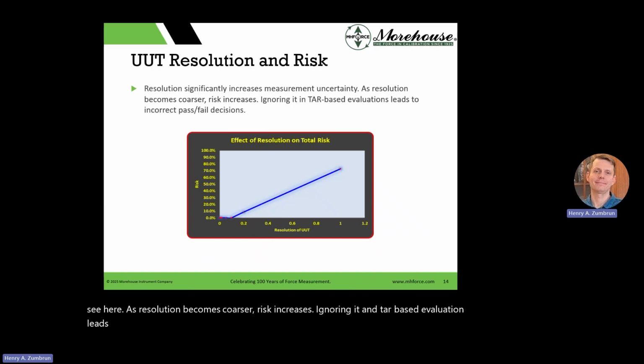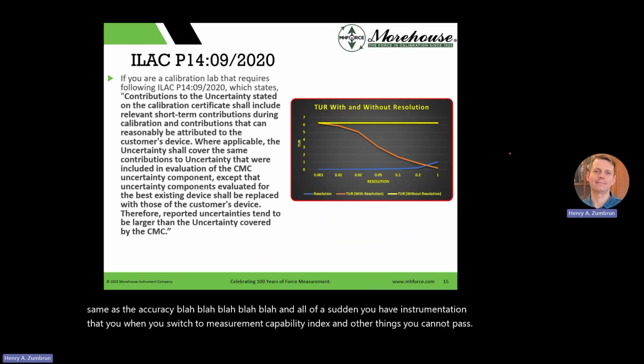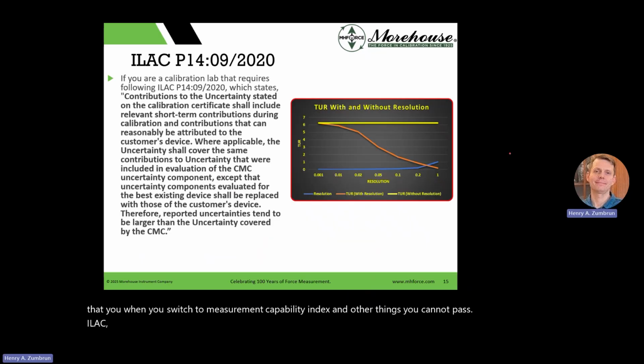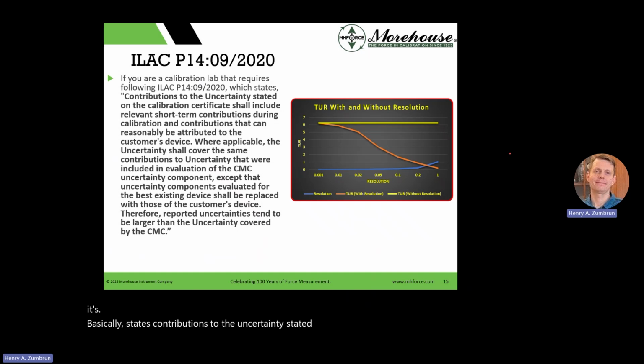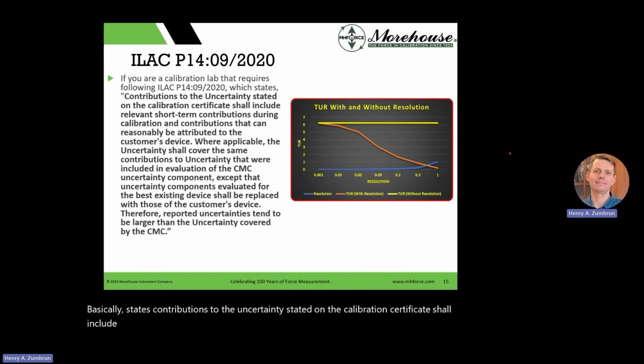So this is what happens. Manufacturers say, hey, the resolution is the same as the accuracy, and so on. And all of a sudden you have instrumentation that, when you switch to the measurement capability index and other things, you cannot pass. ILAC P14, this is a policy document. If you're a calibration lab, you know about it. It basically states that contributions to the uncertainty stated on the calibration certificate shall include relevant short-term contributors during calibration and contributions that can reasonably be attributed to the customer's device.